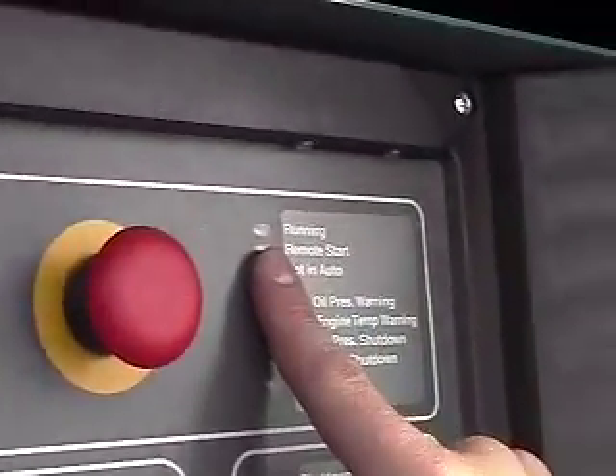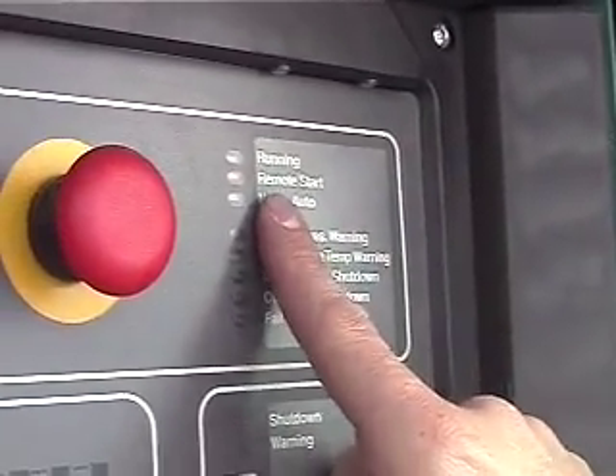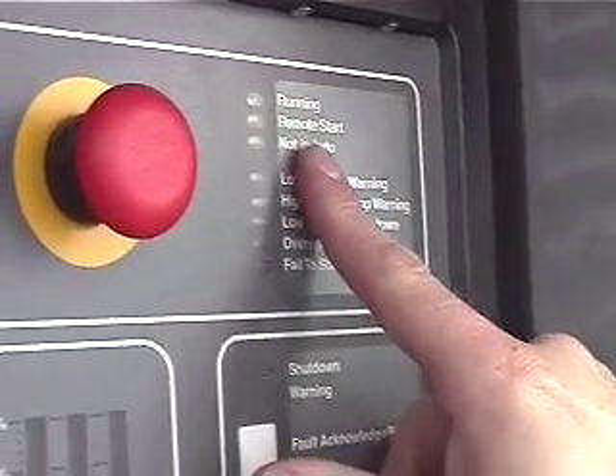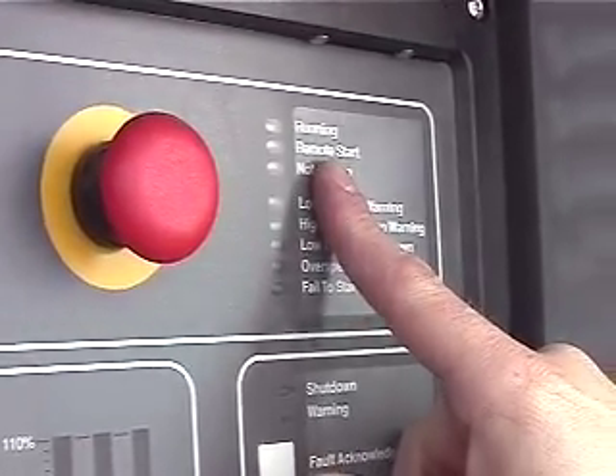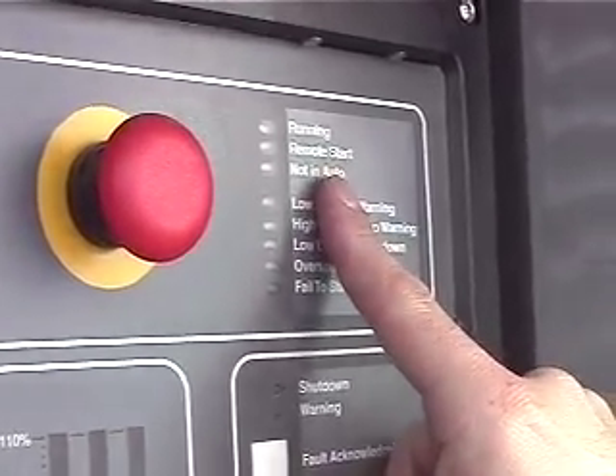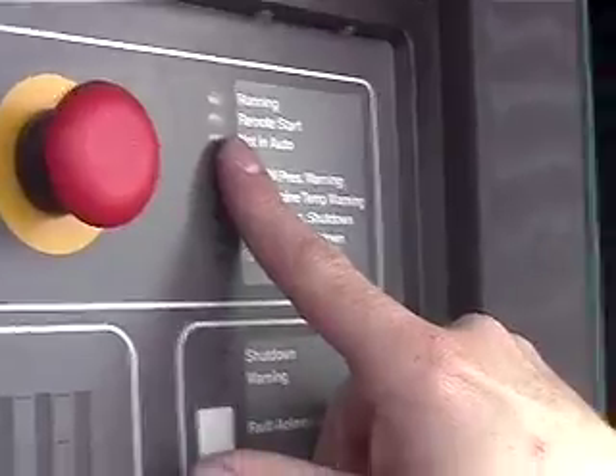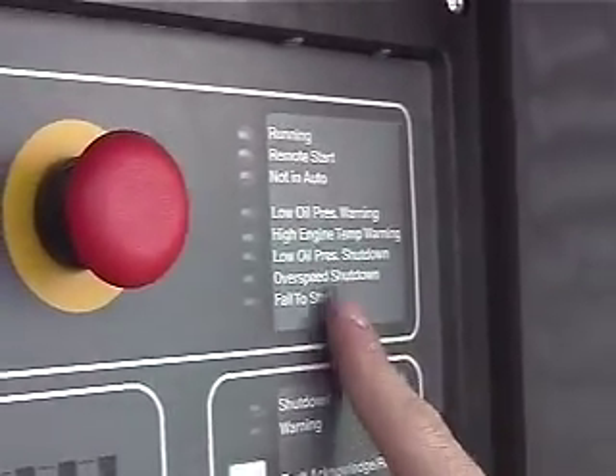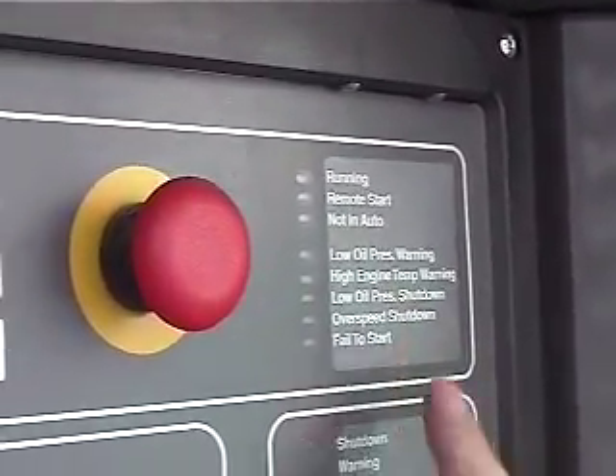Anytime it's running, we should have a running light on. With two transfer switches, anytime either one is telling the generator to start, we should have a remote start light on. The next one, not in auto, will flash anytime it's not in auto. The others are just what they say: low oil pressure warning, high engine temp.